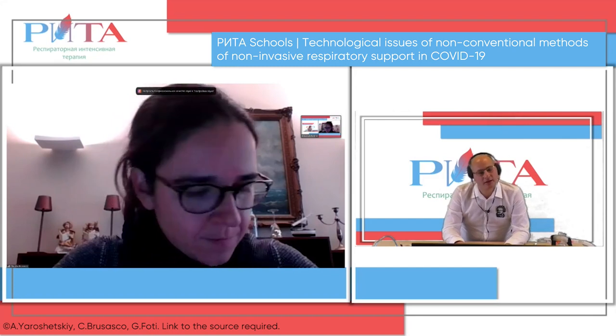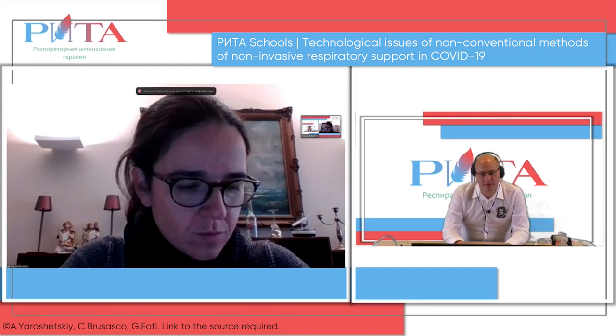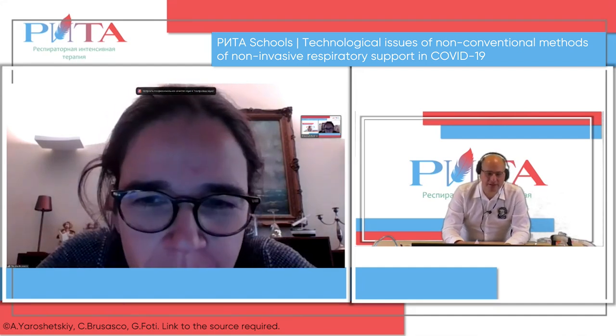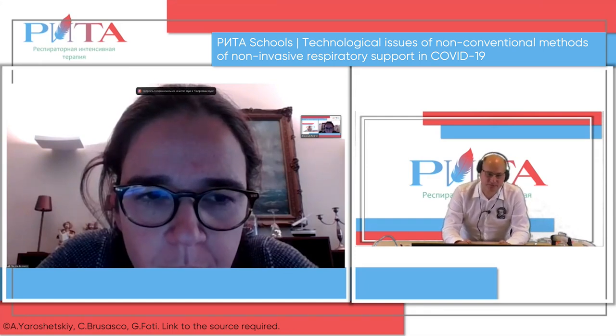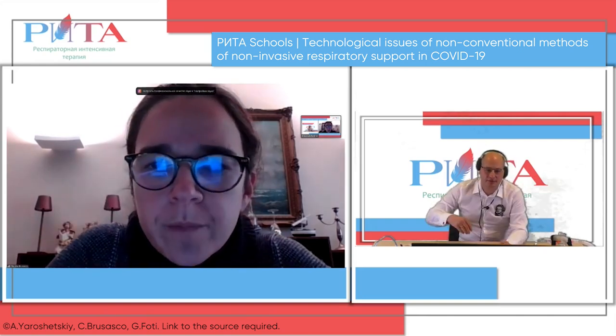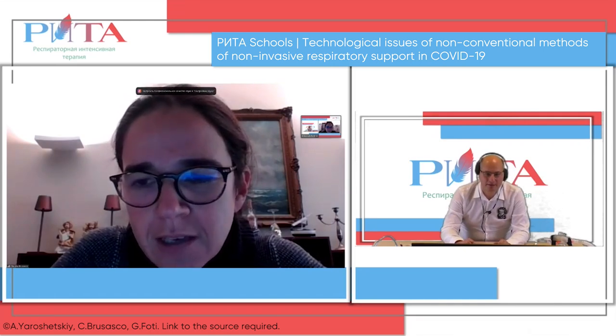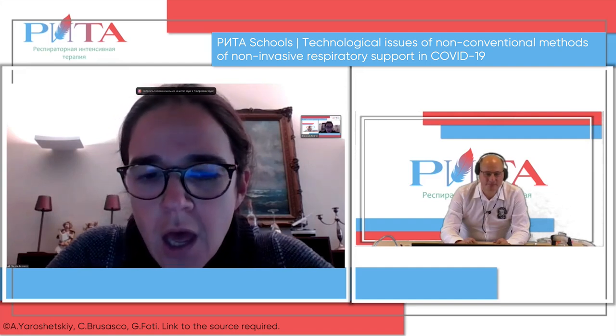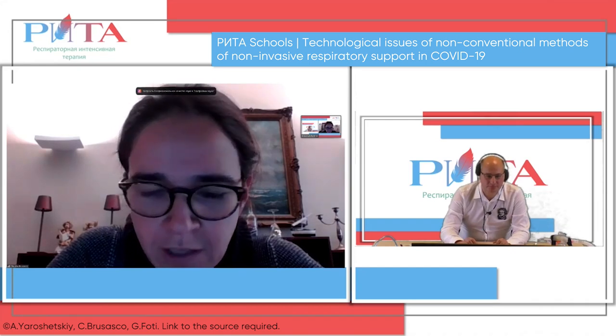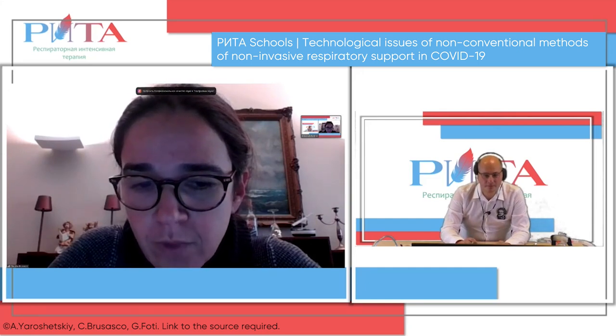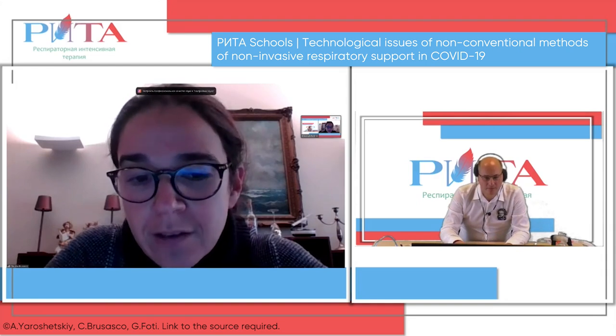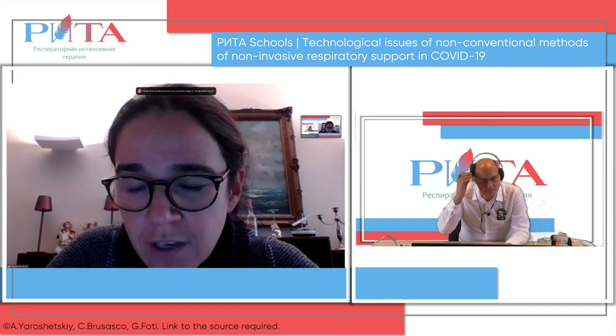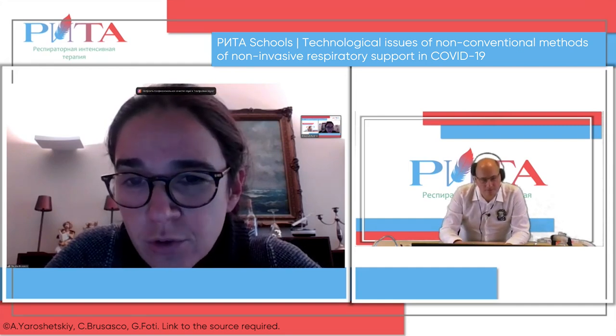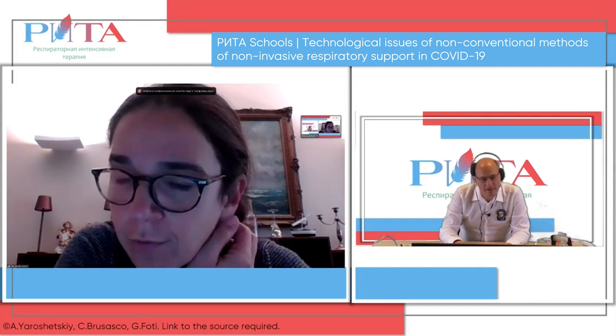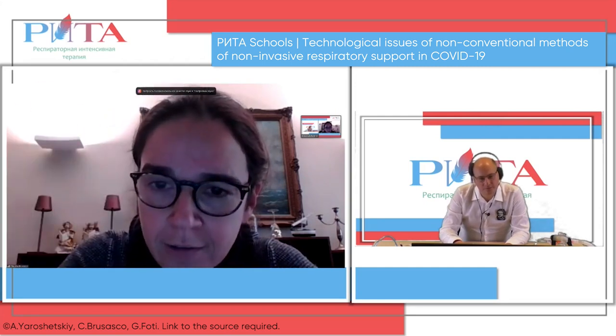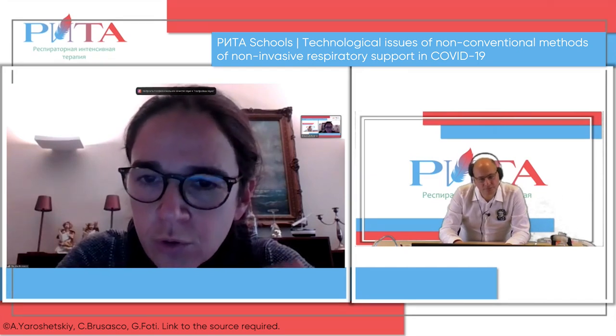Claudia, we're discussing our Venturi system - what is it? Is it a Boussignac system or something else more complicated? Is there a difference between a Boussignac system and a Venturi system? No, there is a big difference, because as I told you, the most important thing is not the PEEP - positive end expiratory pressure is always achievable with a PEEP valve - but it's the high airflow output inside the interface. The Boussignac doesn't do any acceleration of airflow. So if you use 30 liters from the wall, you give 30 liters per minute to the patient.